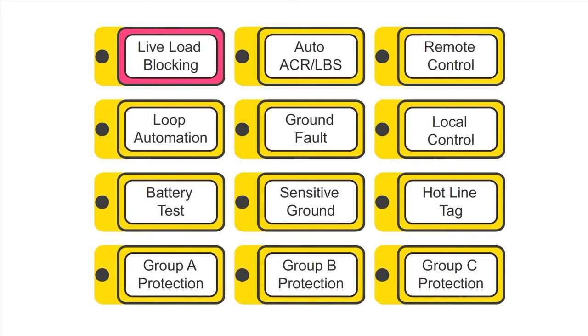Live load blocking prevents a recloser from closing if any of the load side terminals are live. The live load threshold voltage range is from 2 to 15 kilovolts. Loop automation. Turns the loop automation feature on or off. A red lamp indicator shows when the function is on. Battery test. This button performs a battery test, and the result is displayed in the event log. A red lamp indicator shows when the function is on.